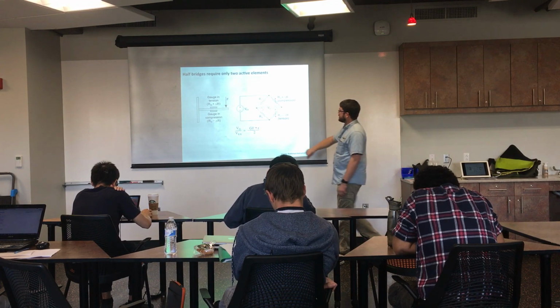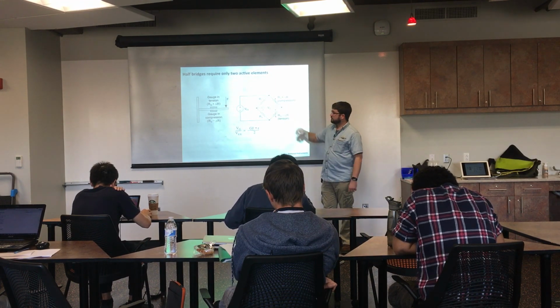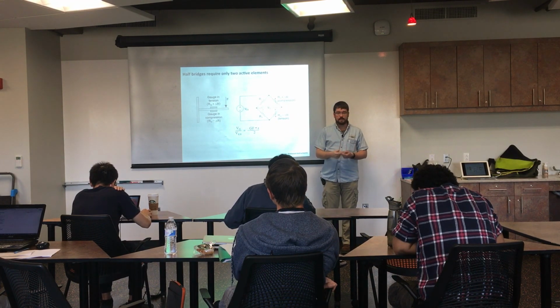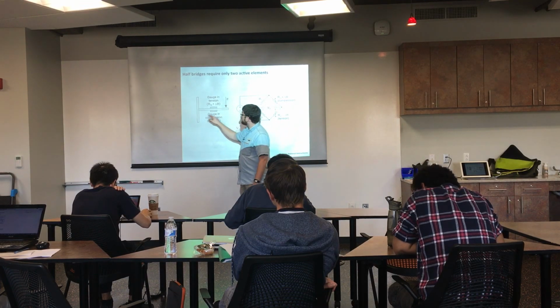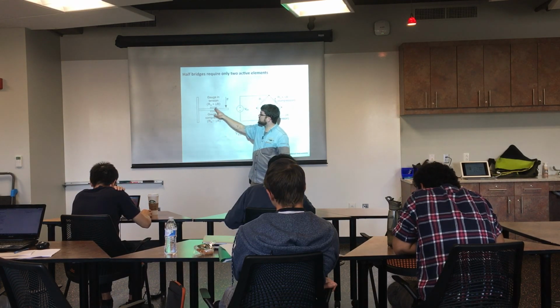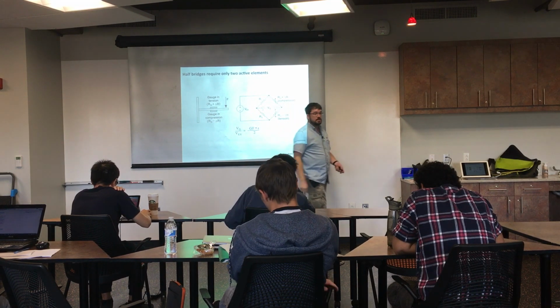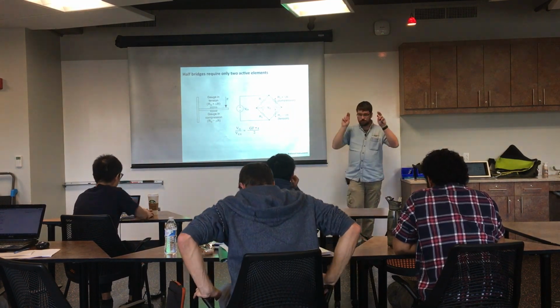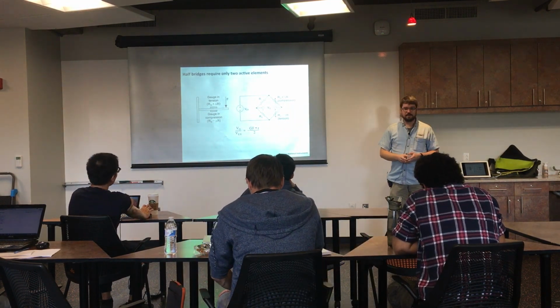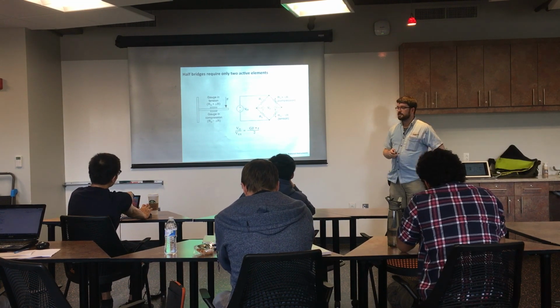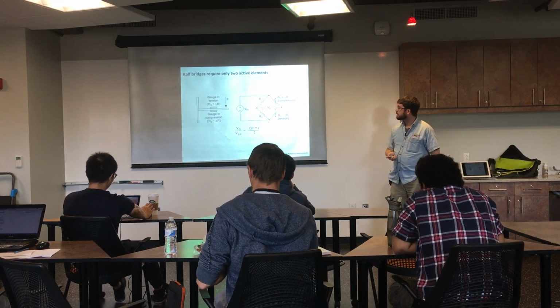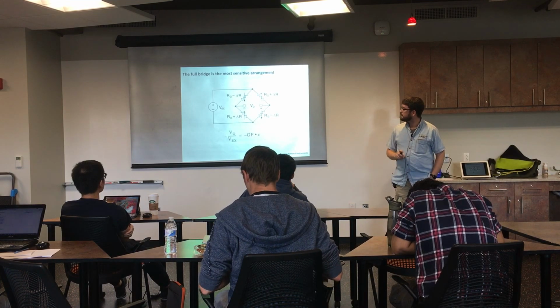In a half bridge, we use 2 strain gauges with opposite sign. For example, if we're bending a piece of metal, you put a gauge on the bottom in compression and a gauge on top in tension. For free, you get greater sensitivity—greater output voltage variation for the same strain. You can see the equation if you need it.